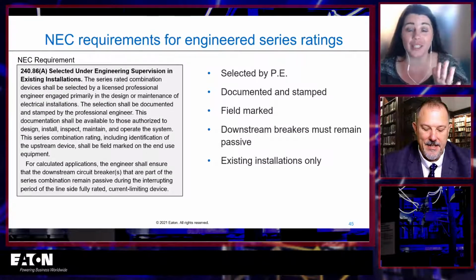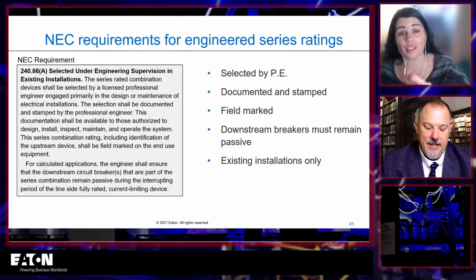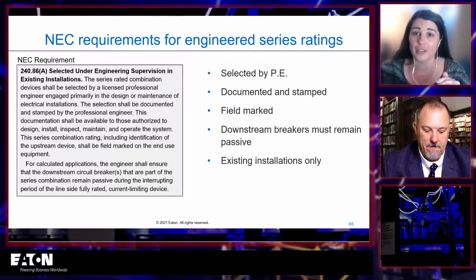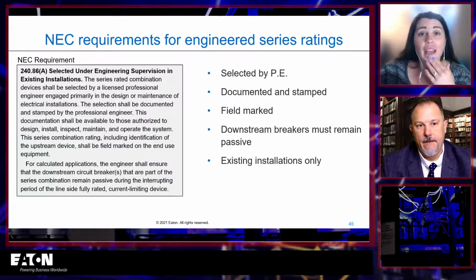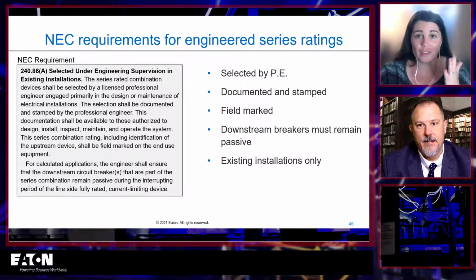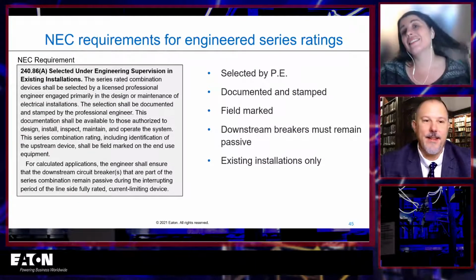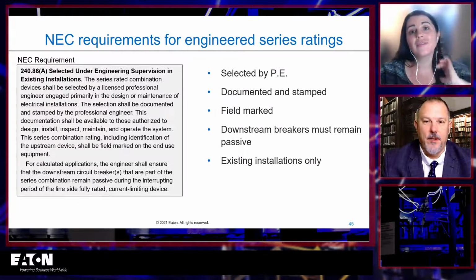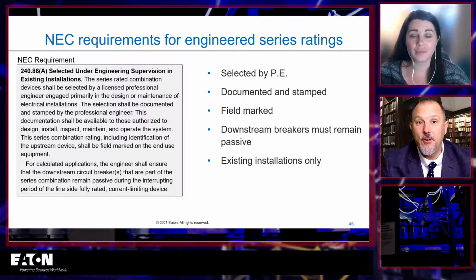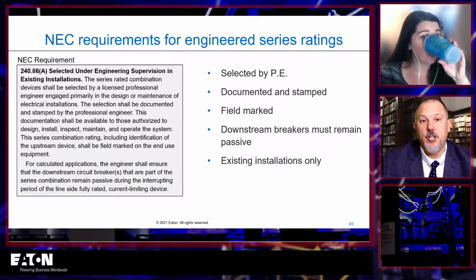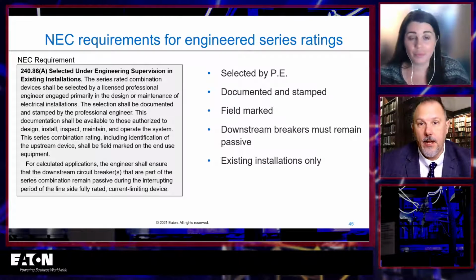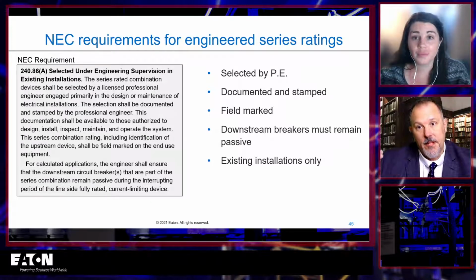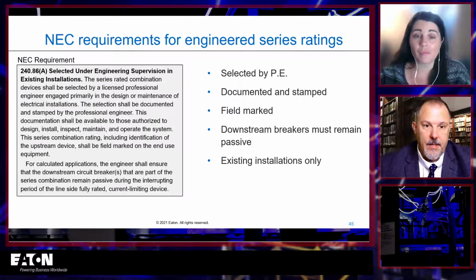If you have to use a series rating, you should be using fully rated systems. But if you have to go to a series rating, good luck finding a PE who wants to put their stamp on that. Yeah, I wouldn't. Whenever we go down these roads, you're doing this because you want to spend less money on the interrupting rating, right? Because the higher the interrupting rating, the more expensive the device.